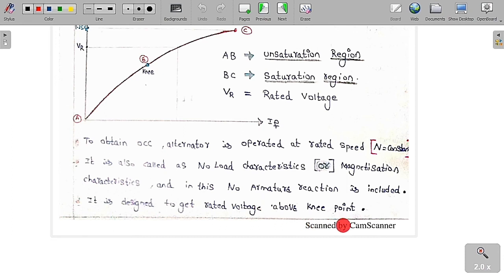We always try to design so the rated phase voltage is obtained after the knee point, or simply, in the saturation region, we try to get the rated RMS phase voltage. These are some important points to keep in mind while conducting the open circuit test on the alternator. To obtain the OCC, the alternator should be operated at constant rated speed. It's also called the no-load characteristic or magnetization characteristic, and armature reaction is not included here. It's designed to get the rated voltage above the knee point.